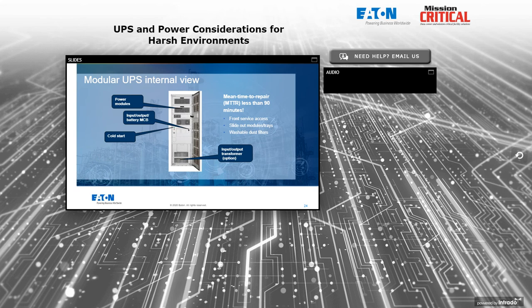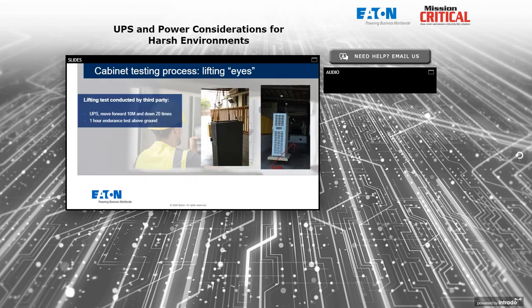So a modular UPS, if you're not familiar, is a big white or black box with a bunch of little UPSs inside that allow them to be slid in and stacked up vertically or horizontally or however, so that I can add more kW capacity and more battery capacity if and when needed. And maybe space for a transformer in the bottom part of the cabinet if the application requires it.